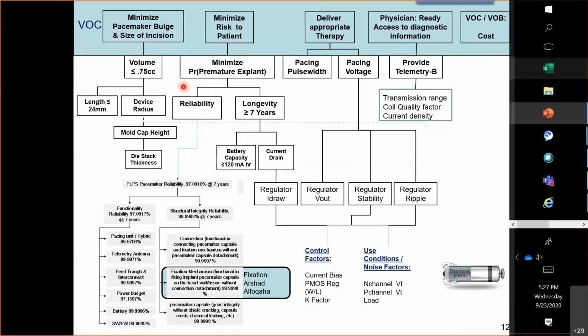And since it's cylindrical, which you see in the picture on the lower right, we need to make sure the length and the radius are consistent with being the small size, less than 0.75 cc. That put a requirement on the length, less than 24 millimeters, and a requirement on the radius. Then that flowed down to a requirement on the die stack thickness. We want to minimize the risk to the patient. That flowed down to requirements on reliability and longevity.